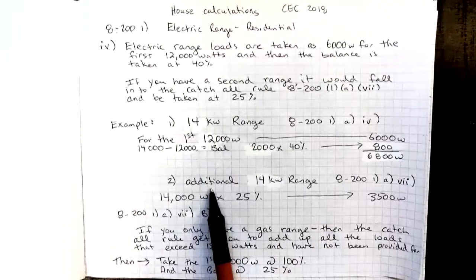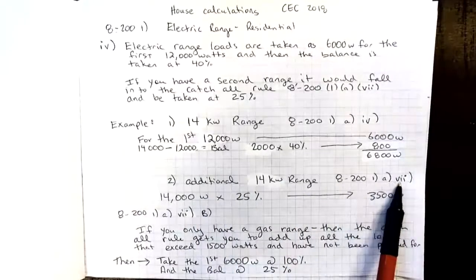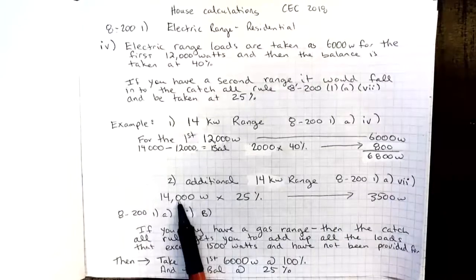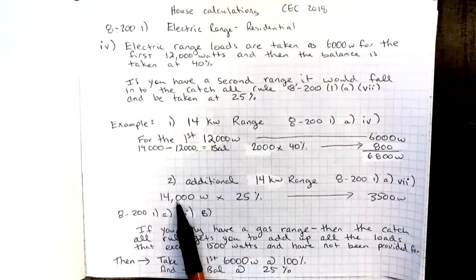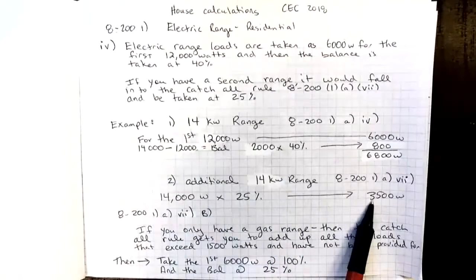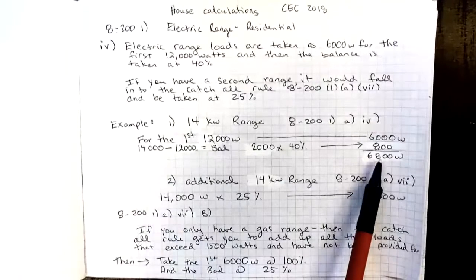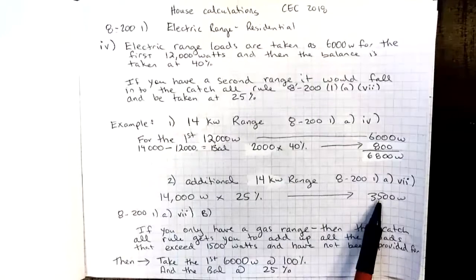Our second range fits into the catch-all rule, which is 8-200 1) a) vii). So for this second range, we would take the total 14,000 watts, multiply that by 25%, and take that demand factor of 3,500 towards service calculations. So both of these added up would account for the two ranges.